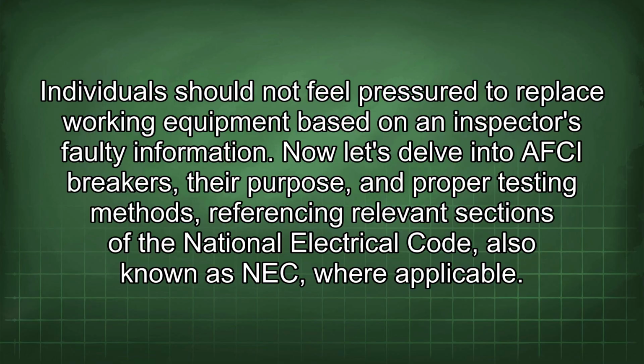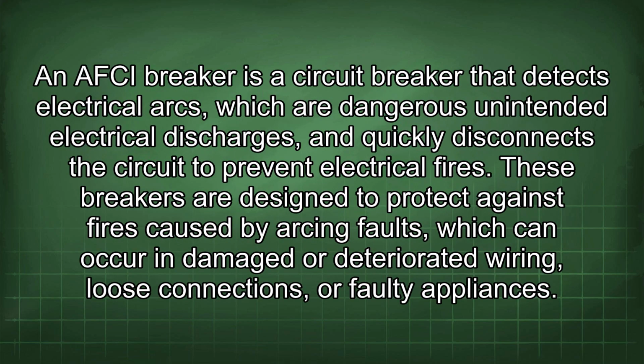Now let's delve into AFCI breakers, their purpose, and proper testing methods, referencing relevant sections of the National Electrical Code, also known as the NEC, where applicable. An AFCI breaker is a circuit breaker that detects electrical arcs, which are dangerous unintended electrical discharges, and quickly disconnects the circuit to prevent electrical fires. These breakers are designed to protect against fires caused by arcing faults, which can occur in damaged or deteriorated wiring, loose connections, or faulty appliances.